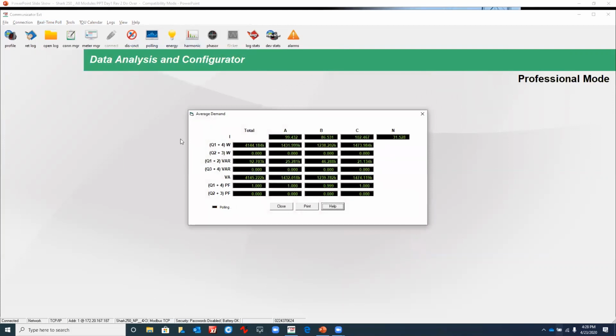So let's continue here with the demand. This is the demand or average demand screen, and this is basically breaking down again with the quadrants, 1 and 4 for delivered watts, or 2 and 3 for received watts, quadrants 1 and 2 for VARs delivered, and quadrants 3 and 4 for VARs received, and your total VA. Again, this is the average information for that period, and it's shown in the screen.